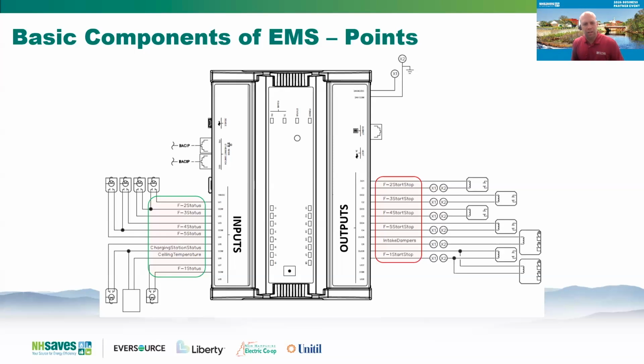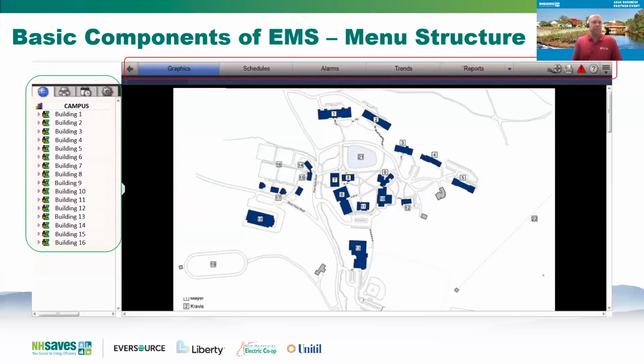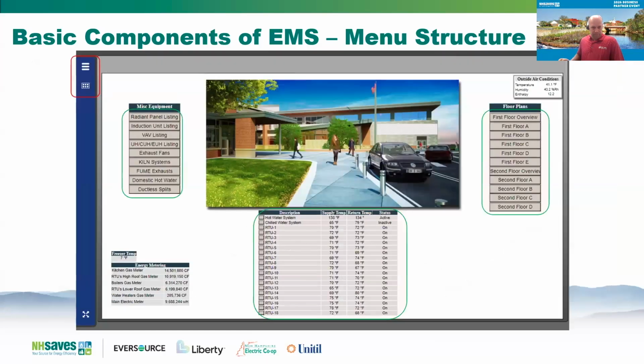So really quick, I want to breeze through some graphics just to show a mix of what's out there. There's a whole host of different manufacturers and different graphic types. Each control system will have its own menu structure. So you can see on this particular front end, they've got their menu structure across the top with graphics, schedules, alarms, and so forth. And on this different manufacturer, they've got their menus on the left-hand side. This one shows an example of a single building where they've highlighted their major systems on the bottom with all the rooftop units. And then they've got some miscellaneous equipment on the left and floor plans on the right.